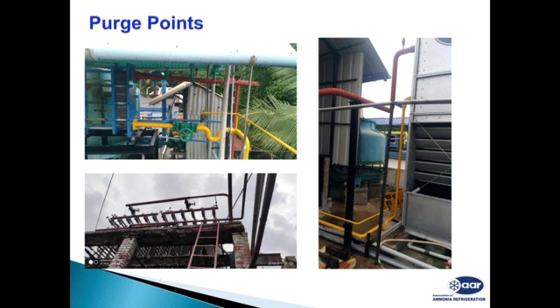These are typical examples showing how purge points are taken. You can see this is a PHE condenser with ammonia coming into the condenser. This is becoming a drain, and this is the purge point. This is a U-trap to avoid any gases going to the receiver. So we have to make sure that our purge point is before the U-trap. Same thing in the evaporative condenser. This is your hot gas coming in, and this is your purge point over here.